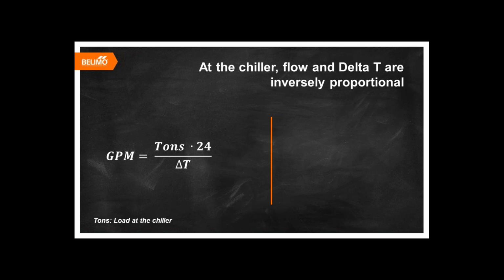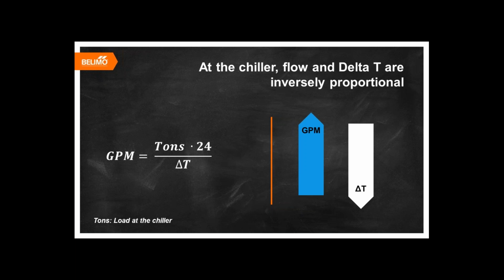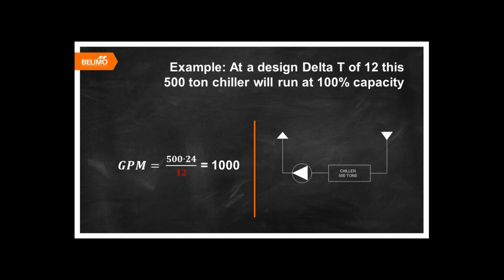Chiller plants can be designed to be very efficient at the proper delta T, but low delta T can play havoc, often resulting in improper staging. Just like the coil, at the chiller, the flow and delta T are inversely proportional. As you can see here, once again, as our flow increases, our delta T will decrease.